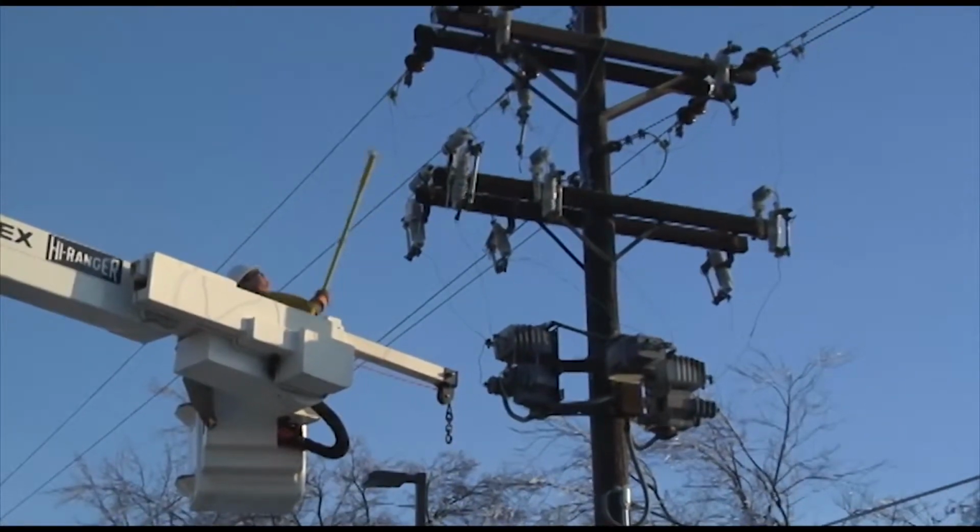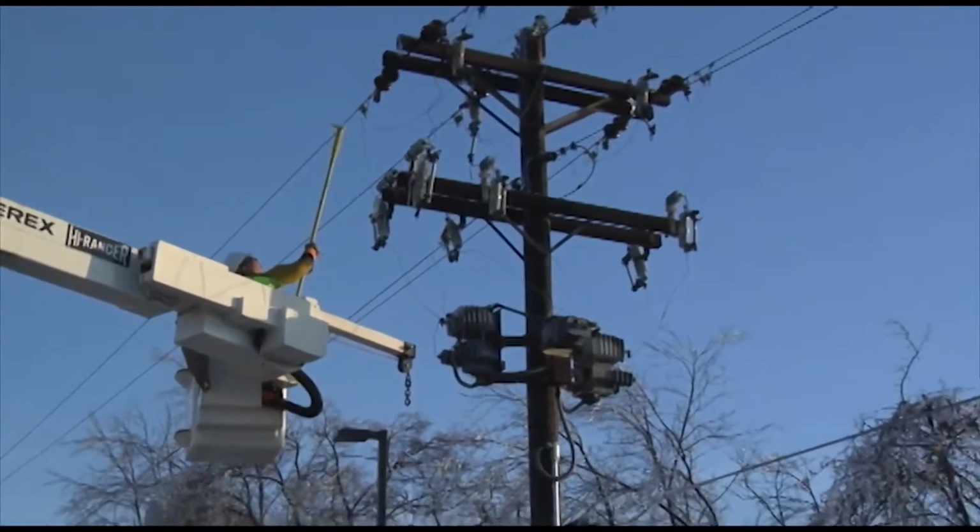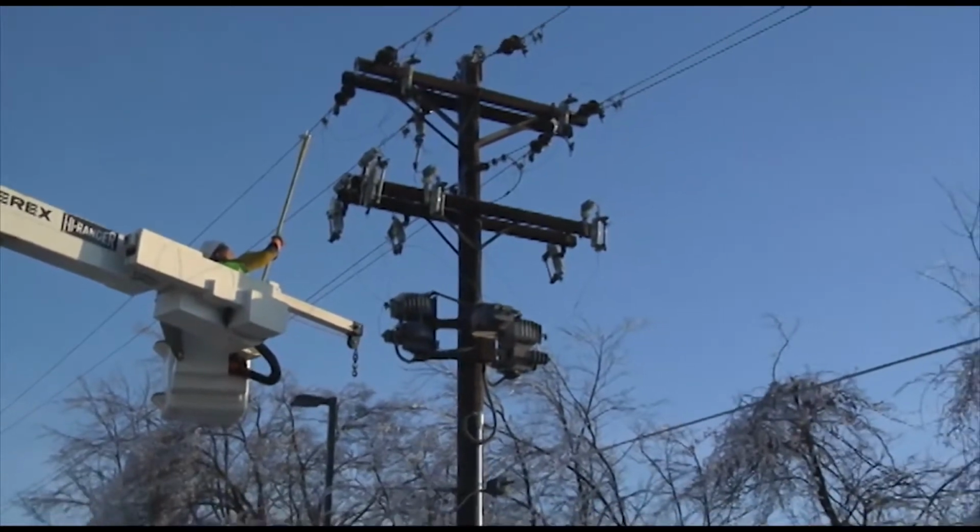If you've got momentaries, if you've got outages caused by trees, or anything else that can come into momentary contact with it, if you put this design up, the aerial spacer bundle design, and you build it correctly, your outages go away. It is very important that we have power to our schools, to our hospitals, to where we can't afford to have any outages. And I believe this product does up that reliability.